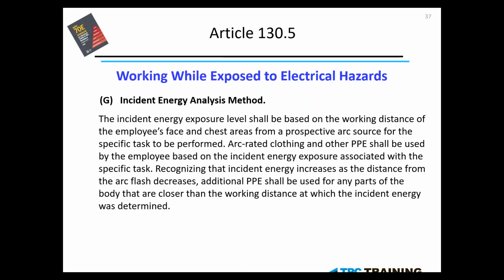Article 130.5, incident energy analysis. Quickly, I want to touch on the labels that are required and when they may need to be required. There are 2 methods by which the information is found on an arc flash label, a warning label. It is the incident energy analysis and the PPE method. If at all possible, we need to do the actual analysis, and if for some reason it cannot be performed, then we do the PPE method.